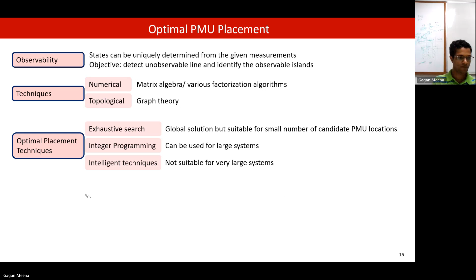A PMU at a bus can measure phase angle of voltage at that bus and phase angles of voltage at the bus at the other end of all the incident lines using current measurement. Zero injection buses, using KCL, can be used to find the angle of one bus using angle for all other buses.